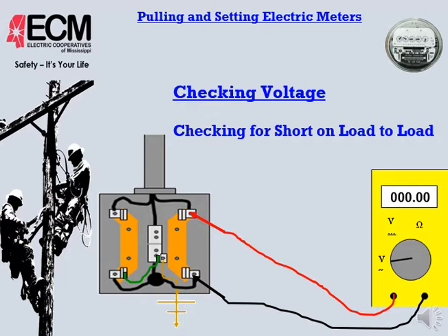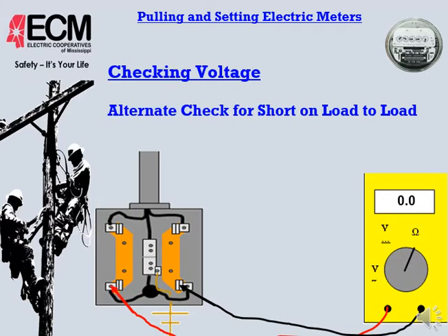Then we're going to check this short on the load to load side. If you'll notice on this slide, they have the neutral and the left load grounded together. They're tied together. Of course, then they're checking the short on the load to load side. You shouldn't get anything, but if you get anything here, then you've definitely got an issue. And then, of course, this is probably the most common of the steps. Most people, including myself, I use this one quite a bit.